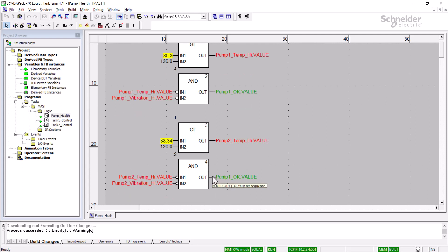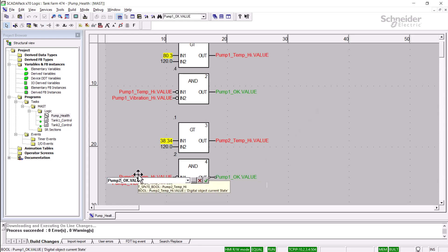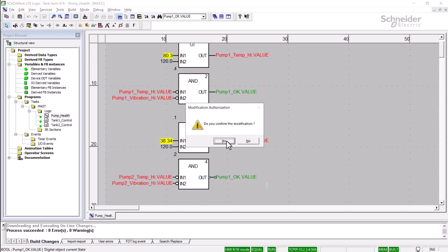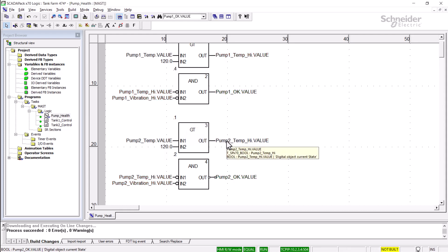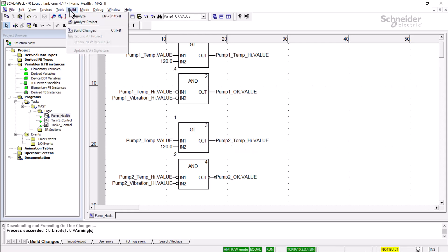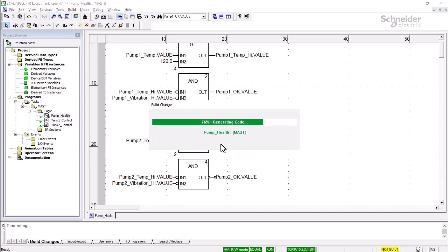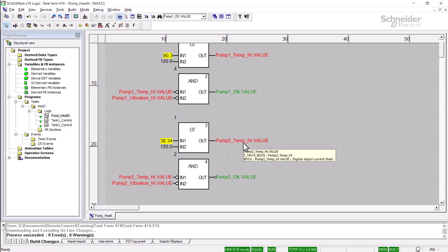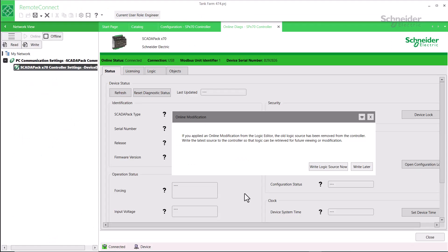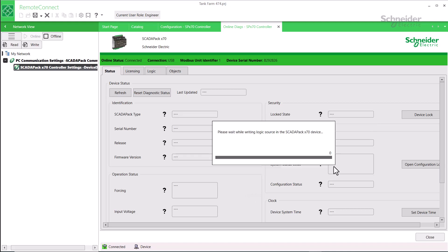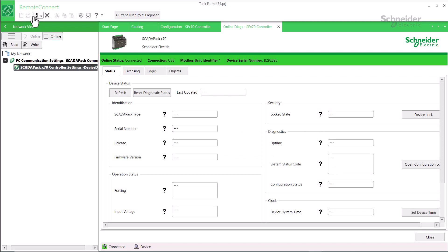I'd like to change the digital output this AND block controls. So I'll double-click on the output, and I want it to control Pump2OK.value instead. I'll click Yes to confirm the modification. Notice the animation goes away. Now to build it, we go to the Build menu and select Build Changes, or we could just type Control-B. I'll confirm this, and we can see that the animation returns. Going back to RemoteConnect, we can see the message about the old Logic source file having been deleted. It reminds me that I can write the latest source file by going to Online Diags and the Logic tab, or I could just click Write Logic Source Now, if that was the last edit I needed to do. After that's done, we'd probably want to save the application.